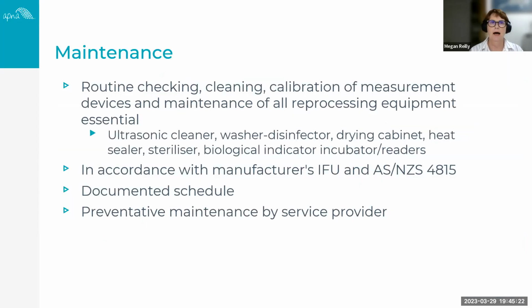Maintenance is critical. And this is not just maintenance of your sterilizer. If you have an ultrasonic cleaner, it may require maintenance depending on what type of cleaner it is. A washer disinfector needs regular maintenance. Some practices have a drying cabinet, so rather than manual drying with lint-free cloths, they have a machine that does it. If you use a heat sealer for sealing your laminate roll, your sterilizer, or a biological incubator or reader for your biological indicator measurements, all of these need routine checking, cleaning, calibration if they're a measurement device, and maintenance. So having that maintenance schedule is critical.